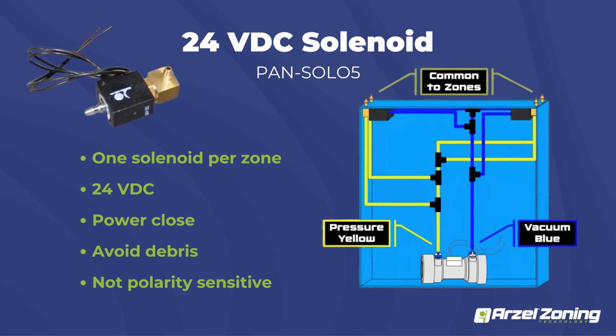If you ever have to troubleshoot the solenoids, they are DC volt solenoids. So they're 24 volts DC to close, 0 volts DC to open. And really, the failure rate is very minimal on the solenoids themselves. The biggest thing to keep in mind is avoiding debris. So if you're installing a panel and it's new construction, they're doing a bunch of drywall work, make sure you leave the caps on the top of the panel on the solenoids until you're ready to actually attach your tubing. Typically, if we have to warranty a solenoid, when we get them back it's because they're packed with drywall dust, 9 times out of 10. Also, when you're rolling around with our tubing on the back of your trucks, treat it like copper: tape the ends off of it and try to keep debris out of the tubing. It's the same deal.